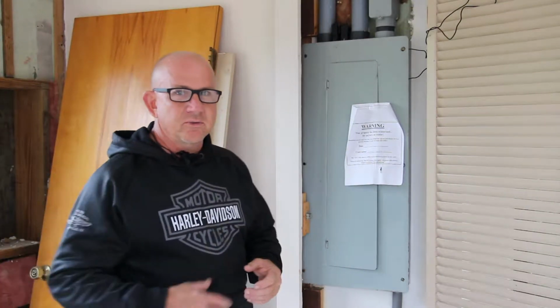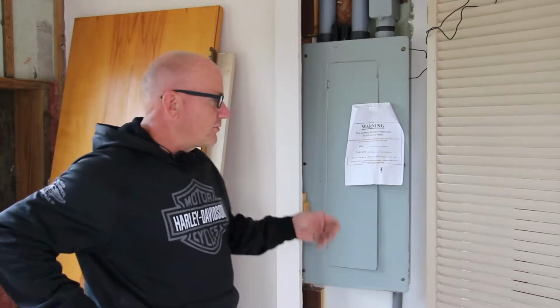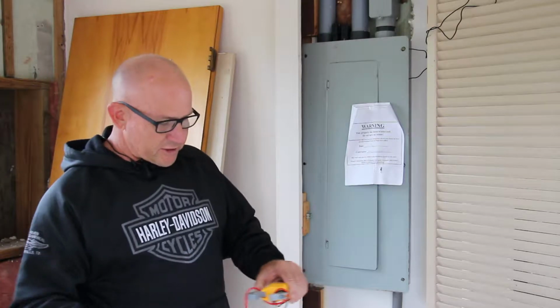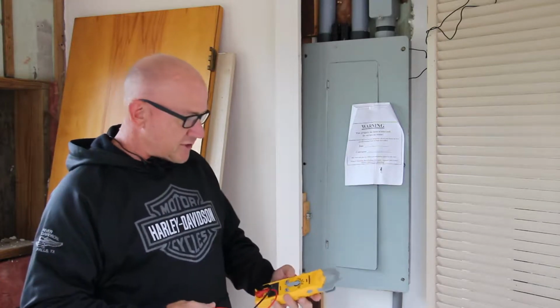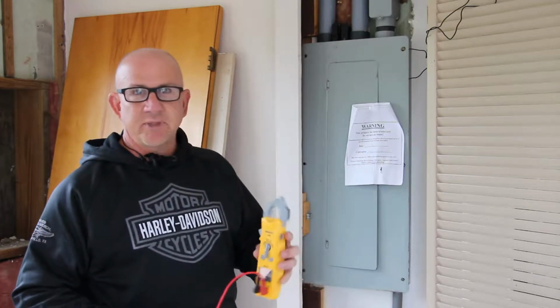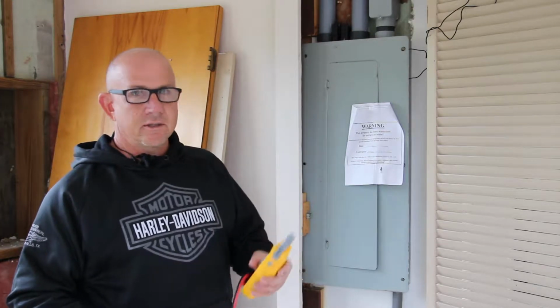Looking at how we inspect electrical panels. One of the first things we want to do when we get to the panel: this house is in pretty poor condition, so a lot of times inspectors may assume that the power is off. Regardless of what the property looks like, before we touch any electrical panels, we want to see if it's energized. I use a Fieldpiece SC420 meter.